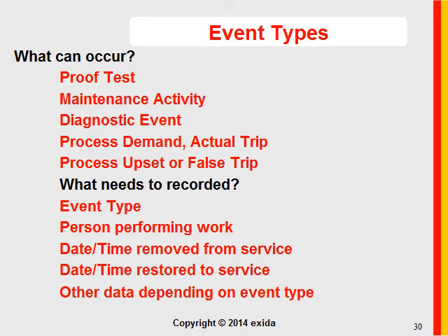And when we started to work on our SIL-Stat software, the main objective was to be able to collect field failure experience, live events. How often does a unit or a piece of equipment fail? How often is there a demand from the process, so that we can compare this to our assumed performance?